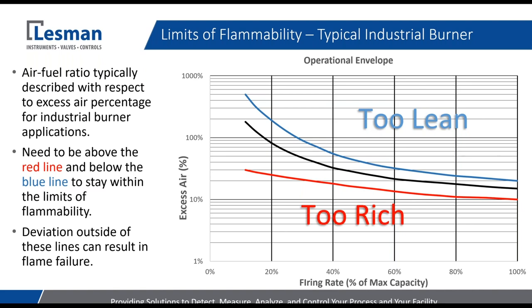Most burners run with 10% excess air and above — they all vary. Some low-NOx, low-emissions burners run a little more excess air to help control NOx production, while others run a little richer to help control CO production. It all depends on the type of burner and the manufacturer's recommendations for air-fuel ratio. Each burner will have a similar kind of operating window between the upper and lower limits of flammability where the burner needs to operate to stay happy. If you deviate outside of these lines, you could cause flame stability issues. As an example, if some system change caused a 10% increase in excess air across the entire range, you could see the curve veer up and at around 65% firing rate enter the 'too lean' area, causing a flame-out.